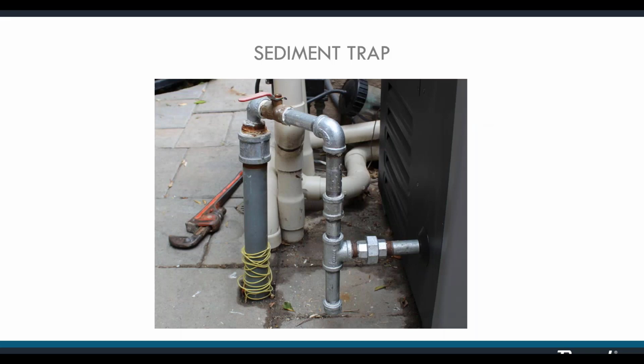This is a sediment trap. They are mandated by the National Fuel Gas Code to be used on every installation. Sediment and dirt can be pushed along by the flow of gas inside the pipe, and the idea is to capture that sediment before it gets to the gas valve. The sediment can start to accumulate inside that gas valve and cause it to fail, and those gas valves aren't cheap, okay? It's important that the gas be traveling downward and then turn toward the heater just before the trap. This way you have gravity and momentum working together to capture the traveling sediment.